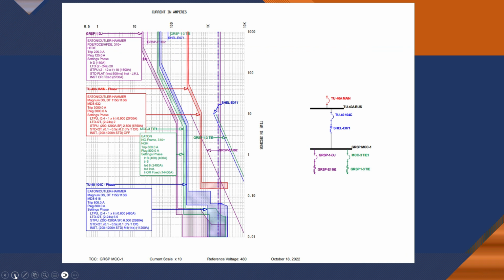Okay, so time current curves. This is a selective coordination time current curve study, an example from an industrial facility right here in Colorado. In order to verify compliance with the requirements for selective coordination, time current characteristic curves can be constructed to show the opening and clearing times of the overcurrent devices for all the values of overcurrents up to the maximum available fault current, which these devices could see. So in order to achieve selective coordination, there can't be any overlap on the time current curve at the fault current, and that would be the problem.